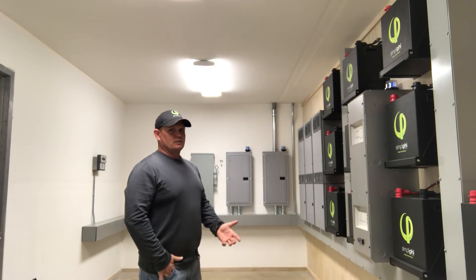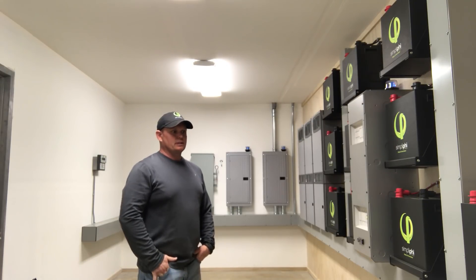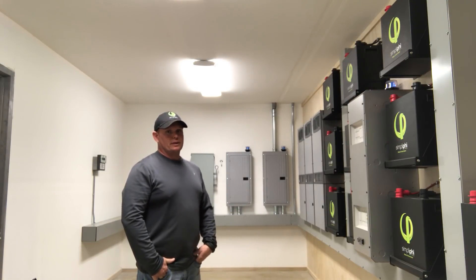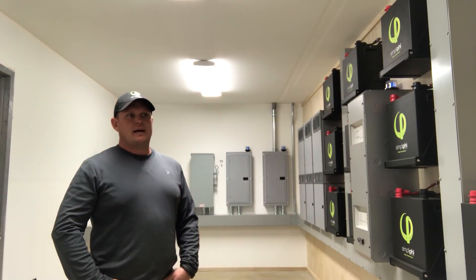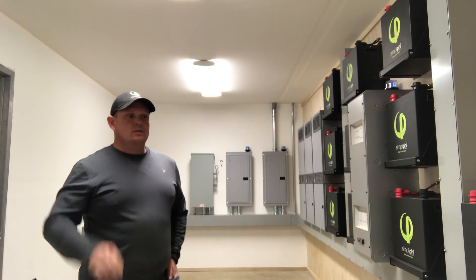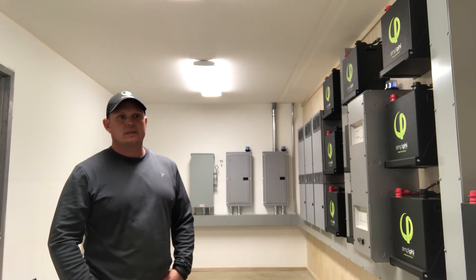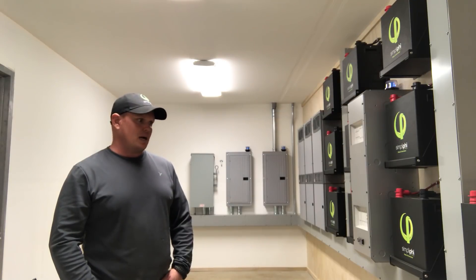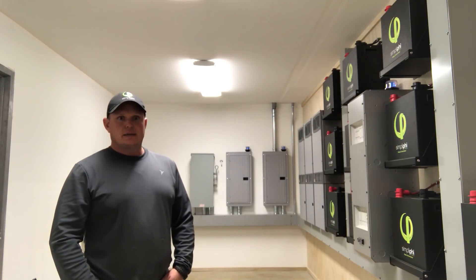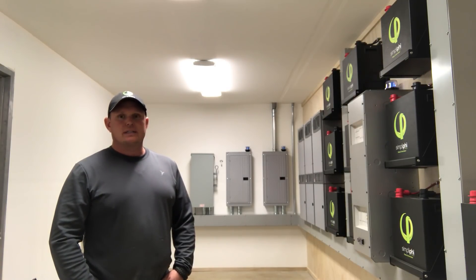Again, it's really a commercial grade power system. We build these systems for mini grids — or I guess you'd call it a micro grid. When you look at the way that the off-grid is going now, we have so much renewable energy capacity that we're able to use generators that don't need to be prime power, because really they're just backup. We don't really expect a lot of generator run time on this project because of the amount of PV in relation to the battery storage and how much we can use of it every day. And again, it's completely set up so that I have more pipes in the ground to allow you to add another 24 panels or whatever I need to do to increase the power as this project grows.